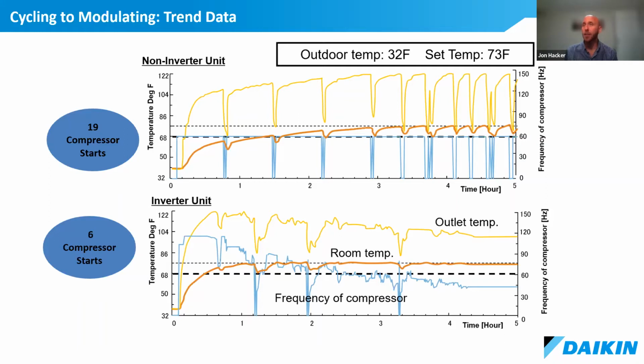And that's a good example of how we're providing better comfort with an inverter product than a single speed on and off. You could see, switching back to the top of this graph, when that compressor turns off, the room temperature, that orange line, deviates pretty significantly, pretty quickly from the set point, right? We're just not getting that from inverter equipment.